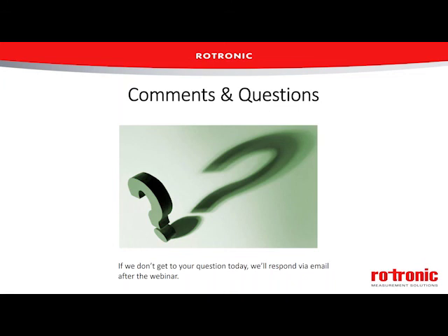Yep. We do have a couple of questions coming in, and we've got time for a few questions. So first question is from Daniel. He said, we measure using a small contained chamber with salt solutions. Are there any concerns once the sensor is installed in a large environmental chamber with a large volume area? I'm going to assume here that Daniel's talking about calibrating his sensors in a small saturated salt chamber and then going in and installing that sensor into a larger environmental chamber.